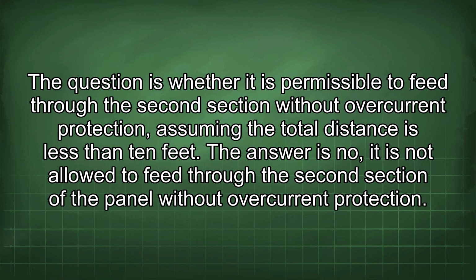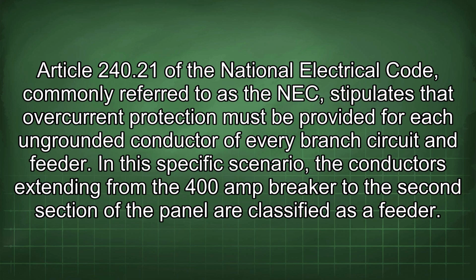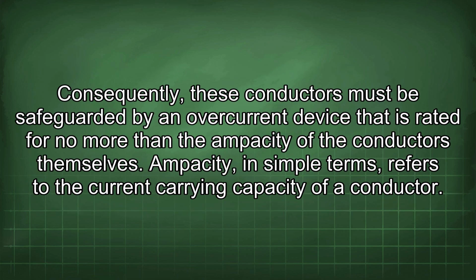The answer is no. It is not allowed to feed through the second section of the panel without overcurrent protection. Article 240.21 of the National Electrical Code, commonly referred to as the NEC, stipulates that overcurrent protection must be provided for each ungrounded conductor of every branch circuit and feeder. In this specific scenario, the conductors extending from the 400 amp breaker to the second section of the panel are classified as a feeder. Consequently, these conductors must be safeguarded by an overcurrent device that is rated for no more than the ampacity of the conductors themselves.